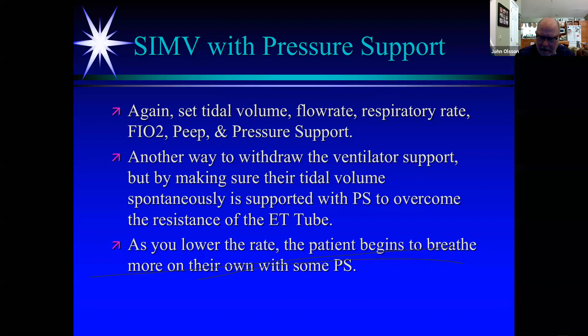So it kicks in only on inspiration. And a lot of times we put it to support maybe to overcome the resistance of the ET tube. As you lower the rate in SIMV, the patient breathes more and more on their own with some pressure support. Like I said, we don't use that a lot here because sometimes patients get confused. They get in a breath where everything is controlled by me, like the volume and the flow rate. And then the next breath, they control a bunch. They control how deep they breathe and how fast they breathe in. So it's sort of confusing. Sometimes it's uncomfortable, and you can see dysynchrony when you use that mode.